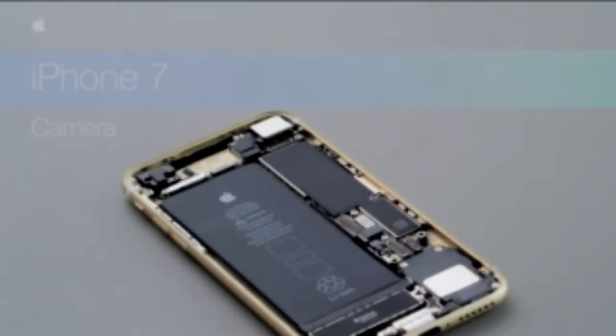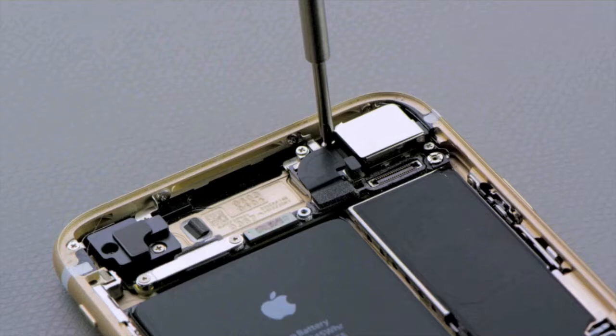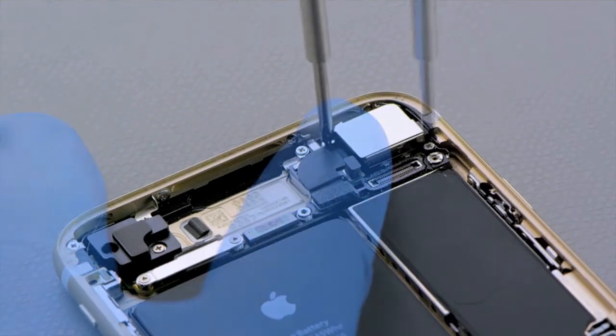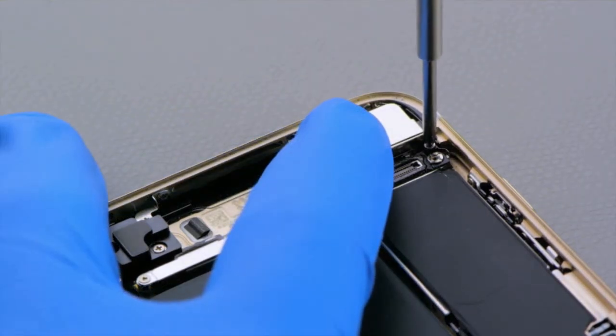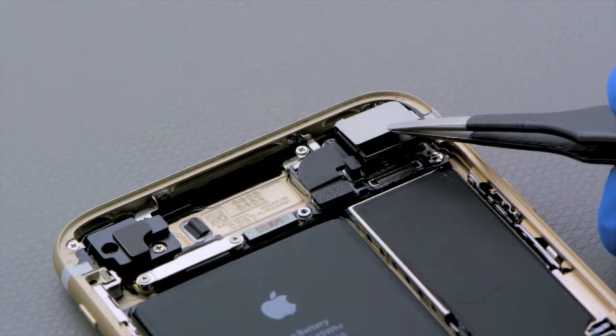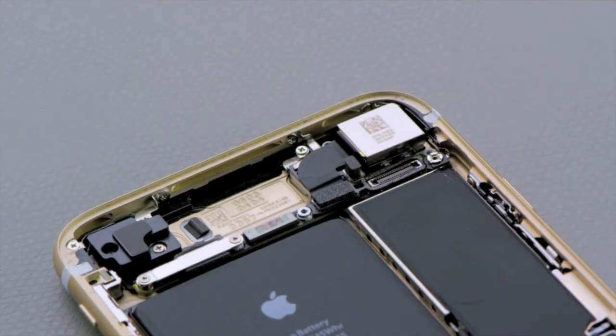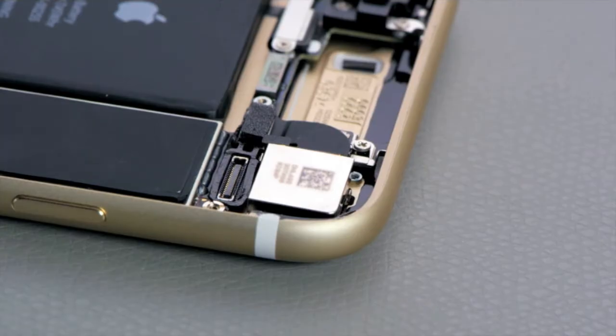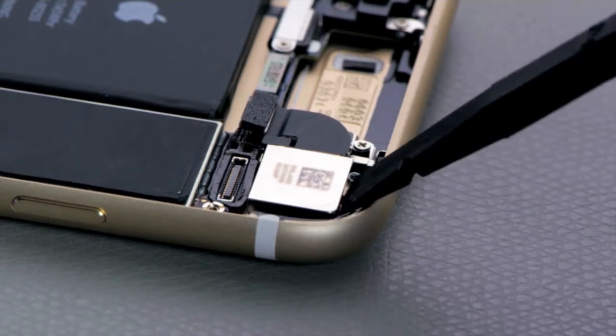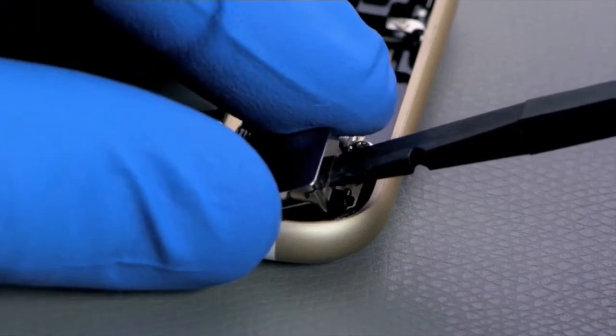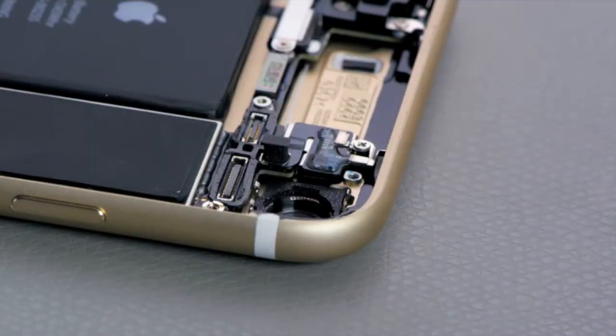Camera. Wear nitrile or lint-free gloves to prevent contamination of the camera lens. Remove and discard the 2 crosshead screws from the camera cowling. Remove the cowling, save it for reuse. Use a black stick to disconnect the camera flex cable from the logic board. Use a black stick to tilt the camera up. Remove the camera from the enclosure.